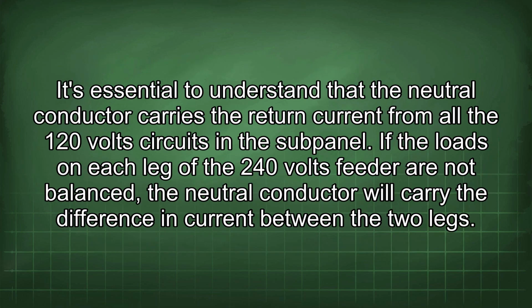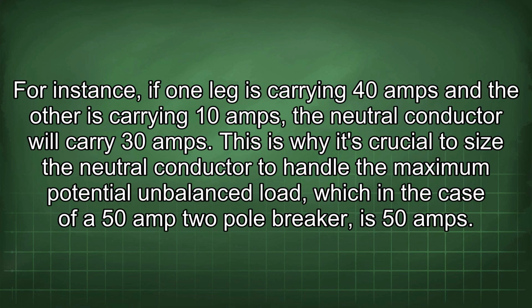It's essential to understand that the neutral conductor carries the return current from all the 120-volt circuits in the subpanel. If the loads on each leg of the 240 volt feeder are not balanced, the neutral conductor will carry the difference in current between the two legs. For instance, if one leg is carrying 40 amps and the other is carrying 10 amps, the neutral conductor will carry 30 amps. This is why it's crucial to size the neutral conductor to handle the maximum potential unbalanced load, which in the case of a 50 amp 2-pole breaker is 50 amps.